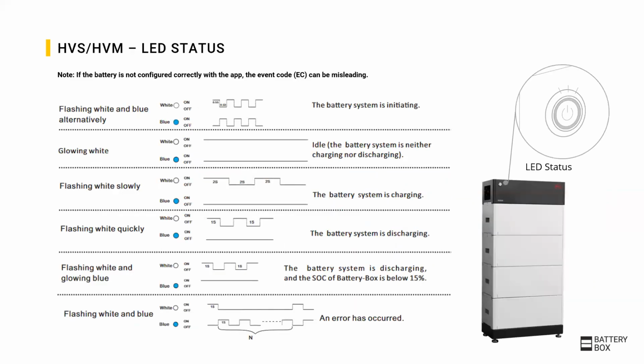When the battery is on, the LED on the BCU will show a status. White blinking is, for example, normal for charging or discharging. A white and blue flashing is normal for the start-up phase or when the SoC is low. But based on the sequence of white and blue blinking, it can also show an error code. For this, the number of blue blinks between white blinking has to be counted. In the service guideline, which will be introduced in some slides, you will find further information and what to do.